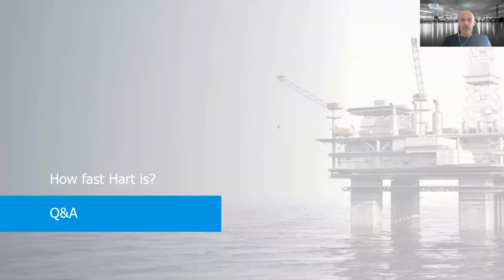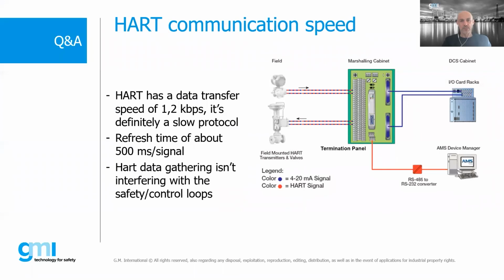Okay, and so how fast is HART? It's not fast, of course. It's a slow protocol, and the refresh time is about 500 milliseconds per signal. But the most important thing is that the loops, safety loop, will not be affected. You just collect the data on your PCs where there is a software, and the software is just for maintenance purpose, monitoring purpose, and nothing else. But it's not fast, of course, the protocol. You can increase the overall refresh time by using more multiplexers on the same network, if you like. That is, of course, possible.